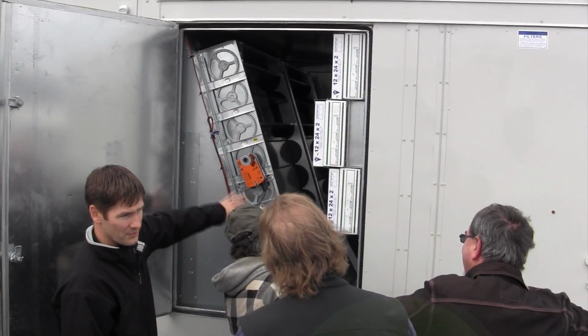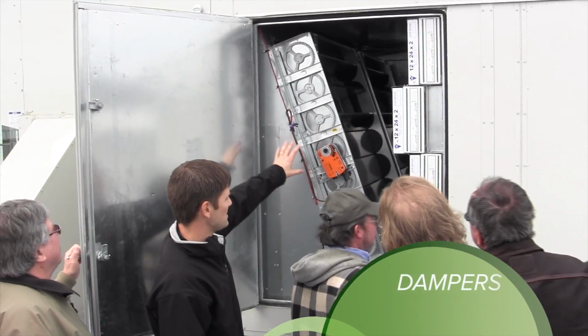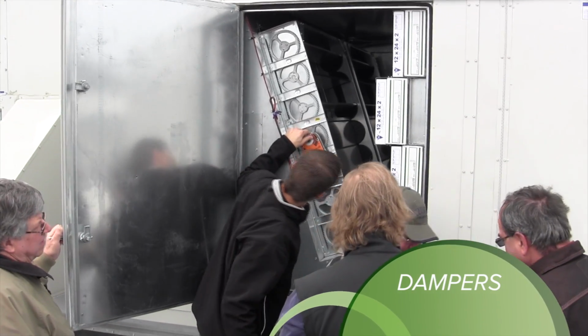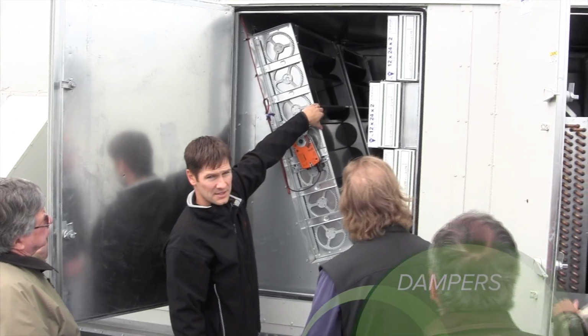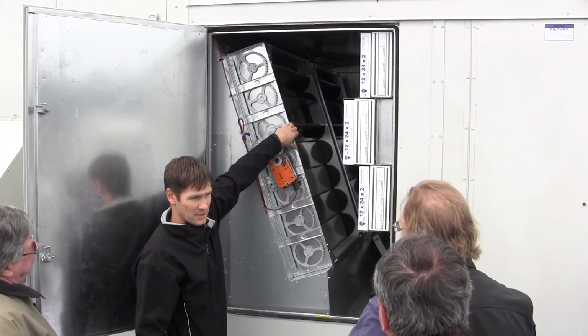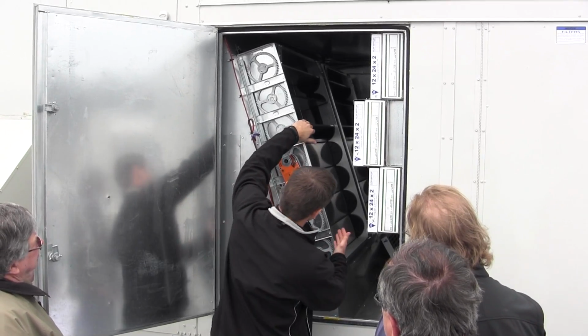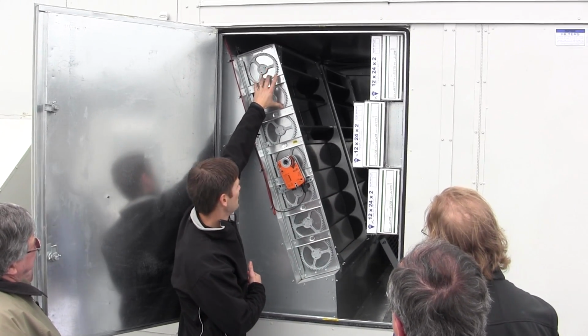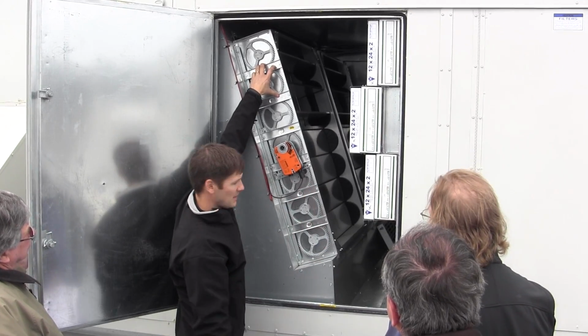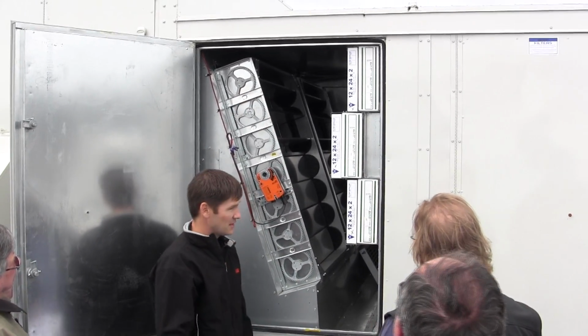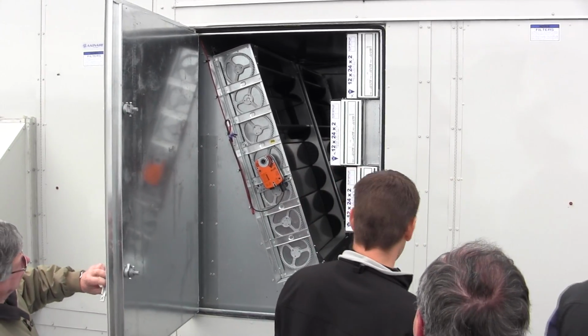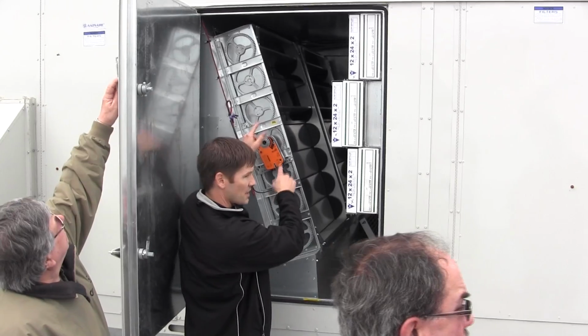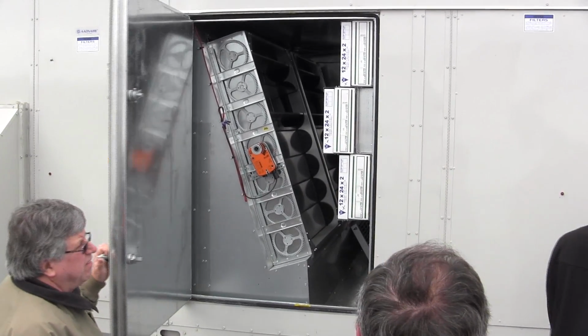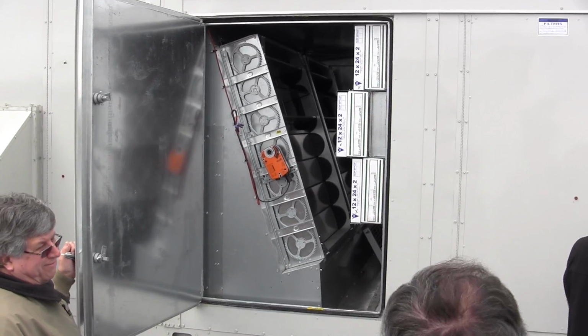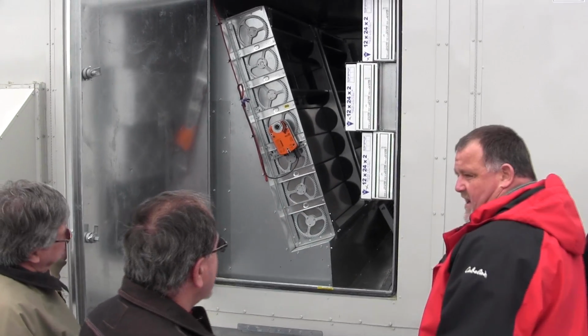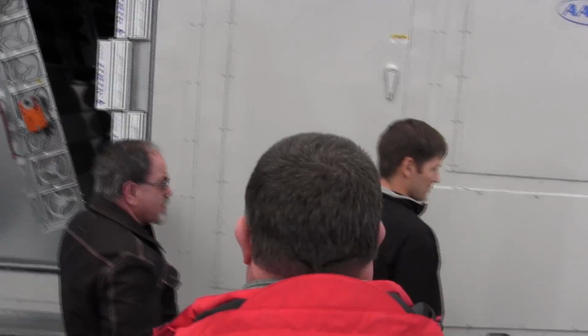So this is usually the economizer dampers. In this case, you can see a division. They'd always be closed unless it's unoccupied hours, and I don't know if it's 24/7. These are outside air dampers, and these will close when it's unoccupied, and these would open up to get the cabinet warm. We can go around the other side to put those other filters in. They're either or. They don't blend. Correct. All these gears mesh together and cause the others to open up. Well, you can modulate, but they're always opposite of each other. So sometimes they'll be in the middle, depending on mixed air temp.